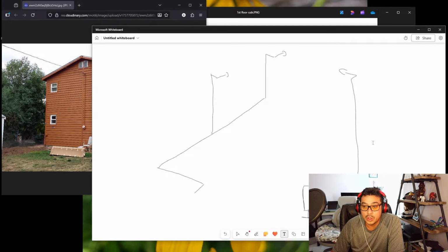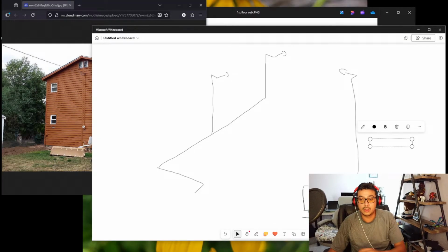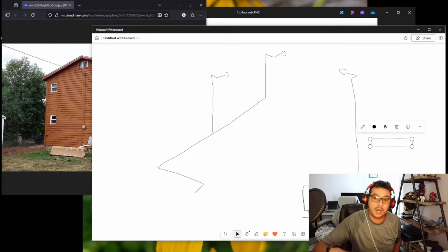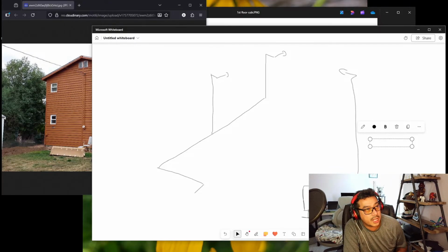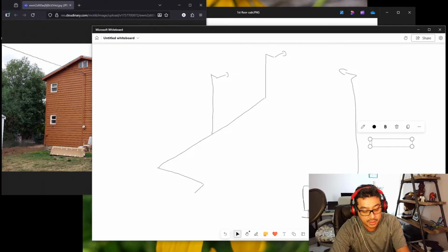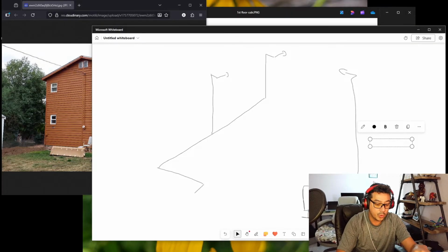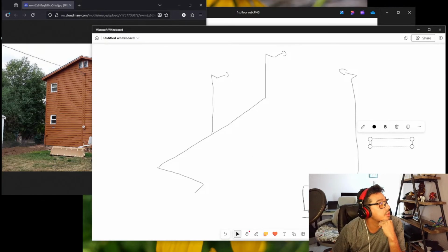Next, we know that the line set up here has to go up 8 feet and then another 8 feet to get to the top, but we don't want to go all the way to the top because we have to have some room above our head unit. So our head unit, let's take a look at this real quick. Head unit mini split. Above a mini split, you need about 6 inches because it needs to breathe.